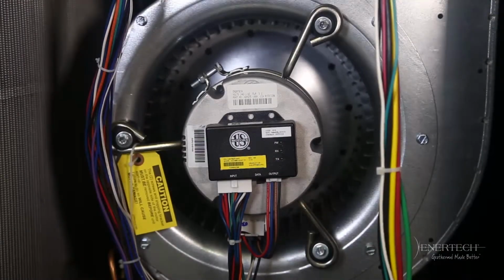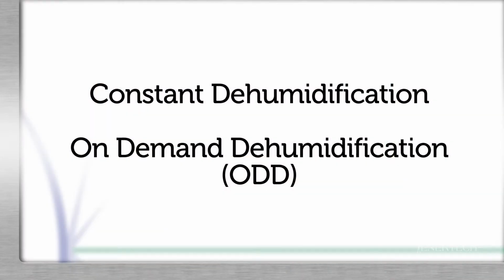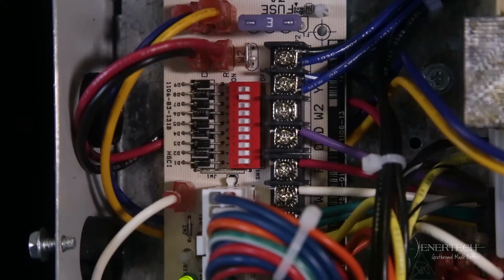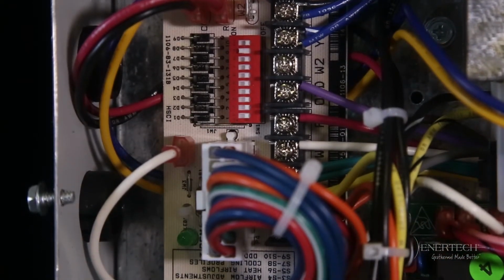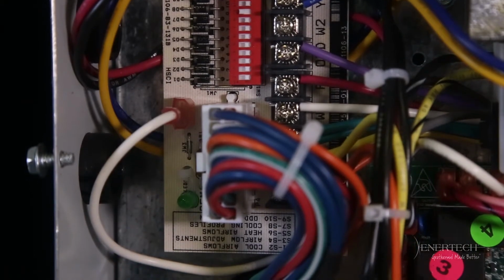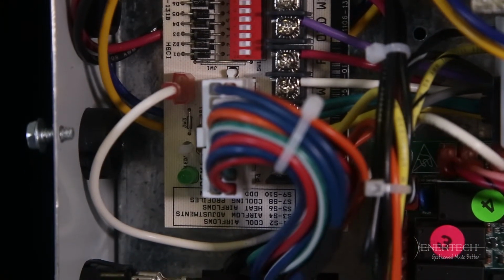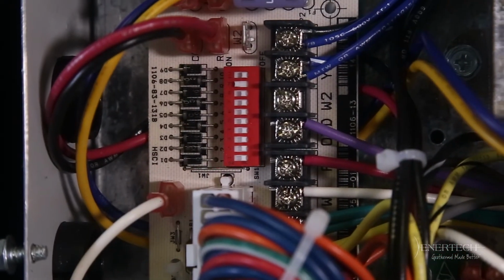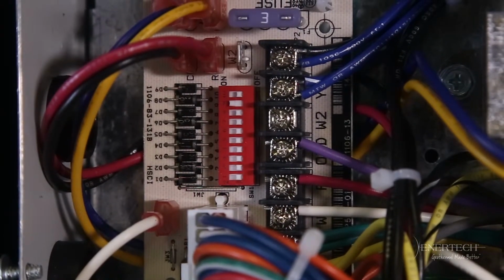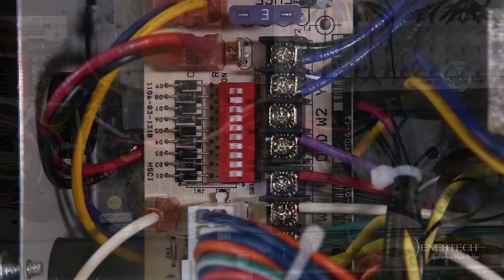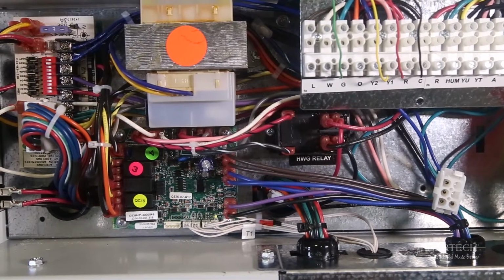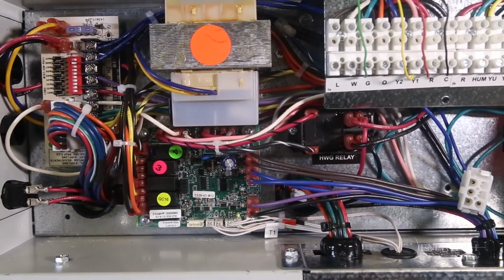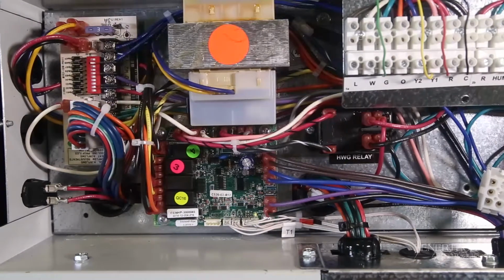When equipped with an ECM fan motor, the ECM fan control board includes 2 types of dehumidification mode: constant dehumidification mode and on-demand dehumidification, ODD. If the ECM control board is set to constant dehumidification mode, the ECM fan runs at normal airflow in all heating stages, but all cooling operation will be 85% of the current stage airflow level based on the dip switch settings. The dehumidification mode lowers the airflow through the evaporator coil to improve latent or dehumidification capacity.